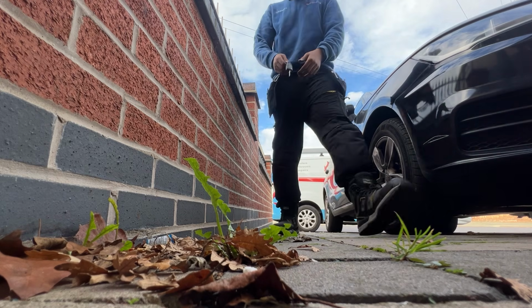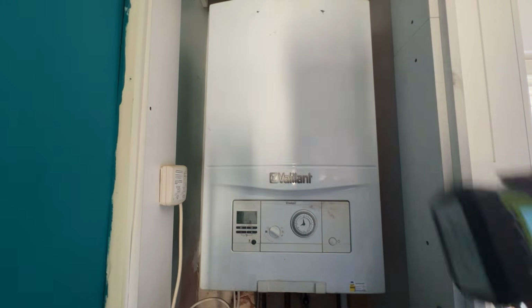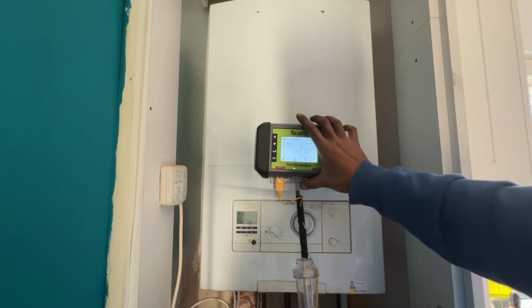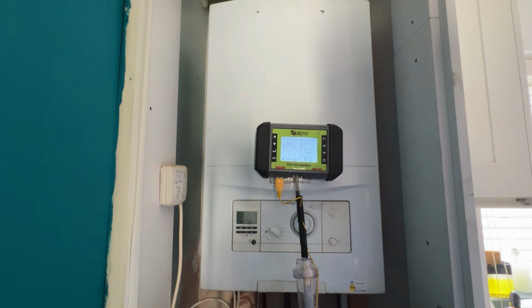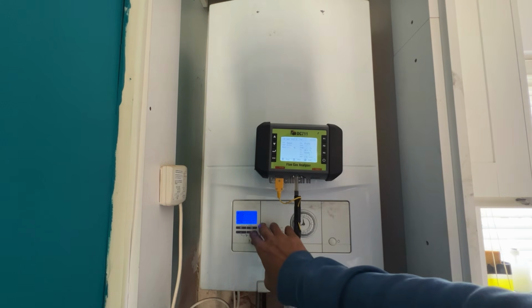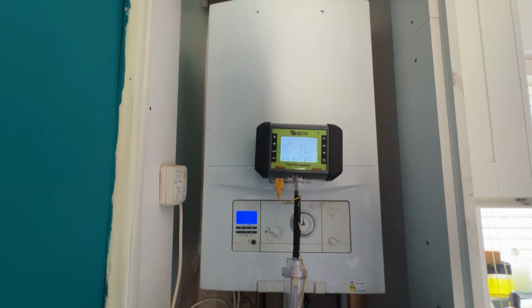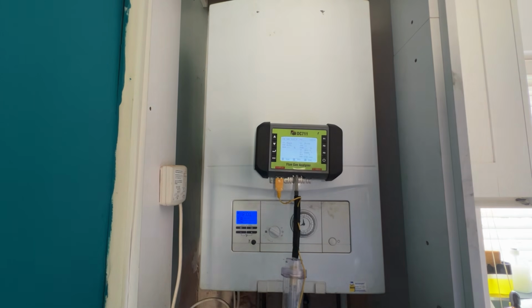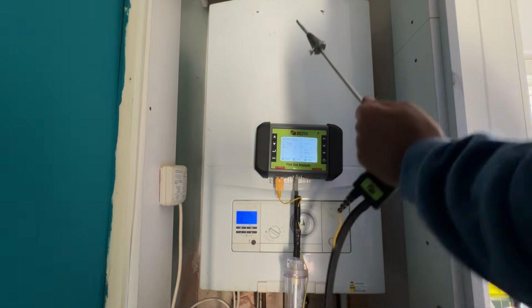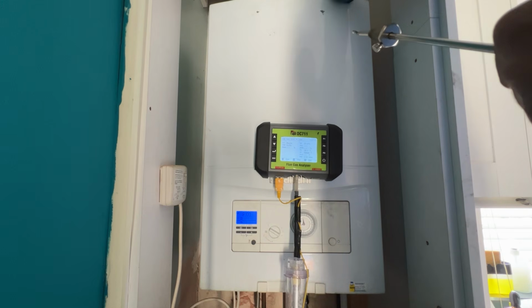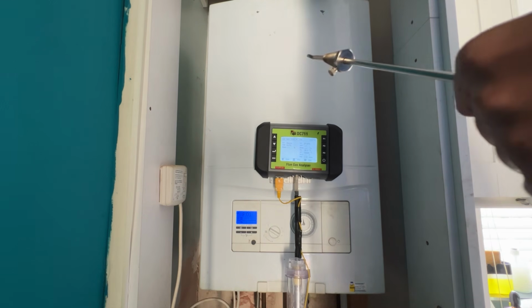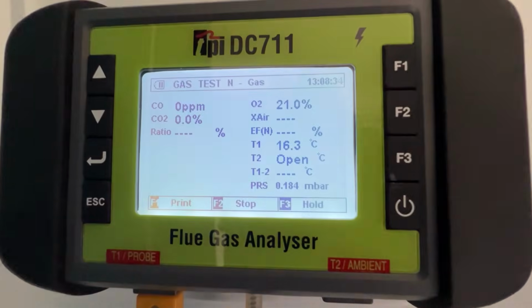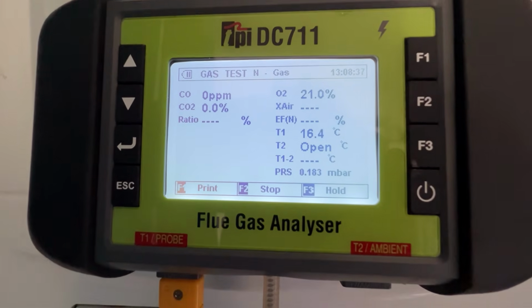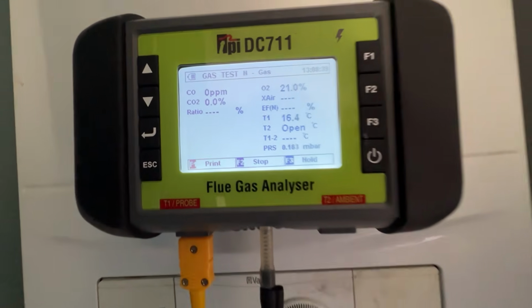Nah, no boilers. Purging's done. Gonna do FGA checks now to check the flue gases. Work it in P01, which is maximum. And I'm gonna check the integrity first of the flue. Make sure air intake is fine. Bang on there. ppm 0, ratio 0, CO2 bang on. Move it along.